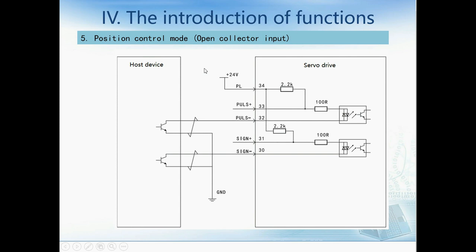This is another kind of wiring — the open collector input. Because there is no 24V power supply in the servo drive, we need to use an external power supply. For example, if the host device is a PLC, we can use the 24V power supply in the PLC. We can treat one wire as Y0 and another as Y1. Y0 controls the direction and Y1 outputs the pulse to control speed.